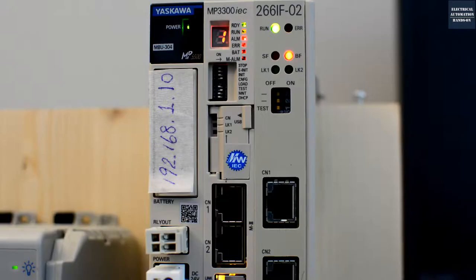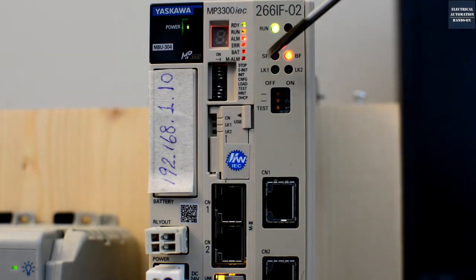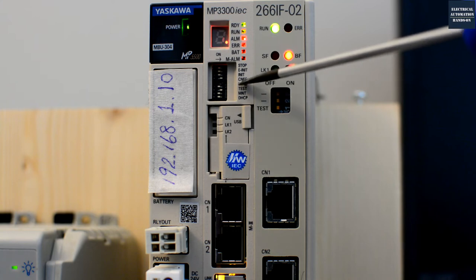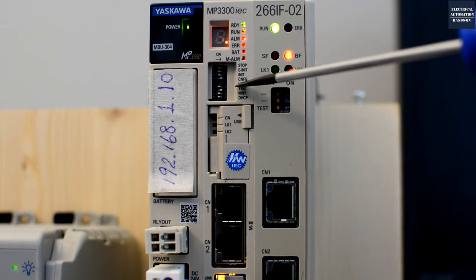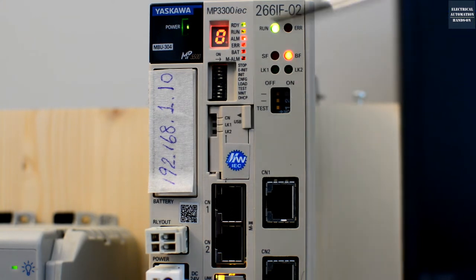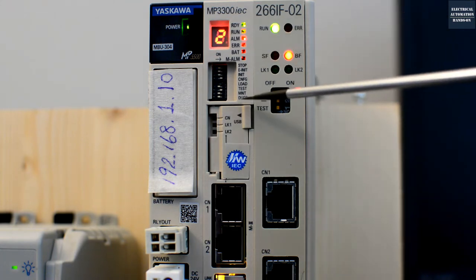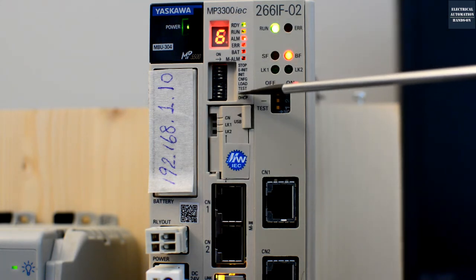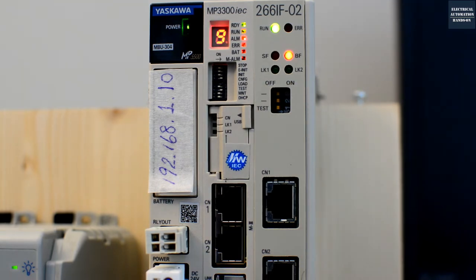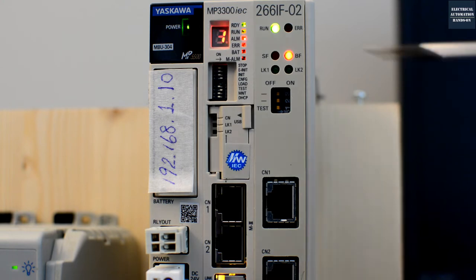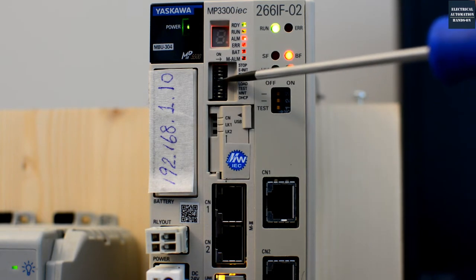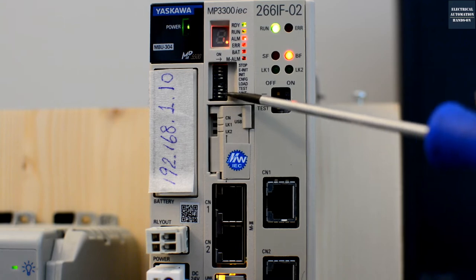After you set the IP address to 1.10, click Save and Reboot. You also need to take care of the DIP switch settings. The CNFG switch should be set to ON so you can configure this controller. The TEST switch should also be set to ON. These are the standard settings for each controller — Config set to ON and Test set to ON.